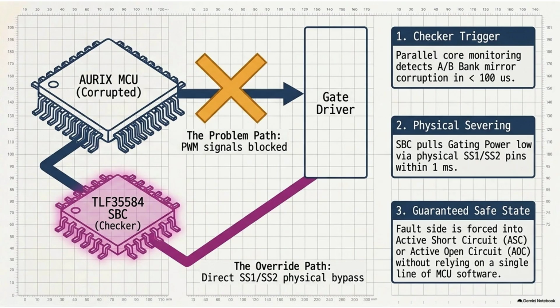Crucially, the checker doesn't try to send a software command through that corrupted microcontroller to shut down the inverter, because it knows the software pathways are dead. Instead, the checker communicates directly with the external SBC, which has a physical hardware pin, an actual direct copper trace, wired straight to the gate drive power supply of the failing motor. When the SBC gets the kill signal, it bypasses the entire software stack and physically cuts the power to the gate drive within 1 millisecond.